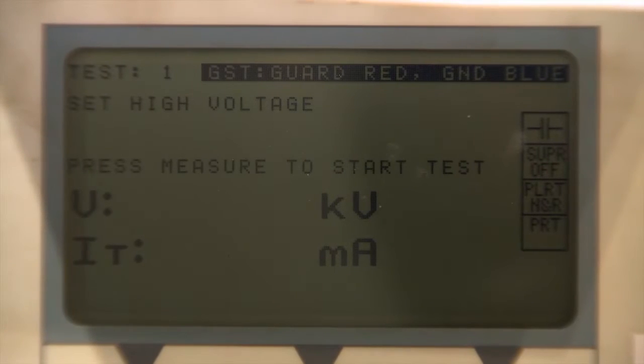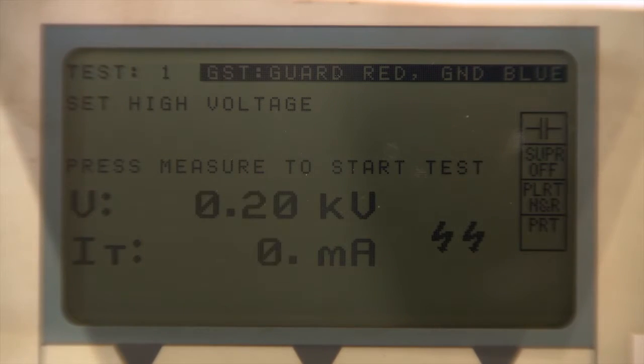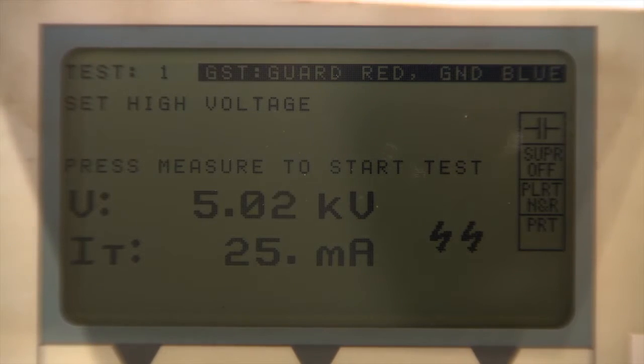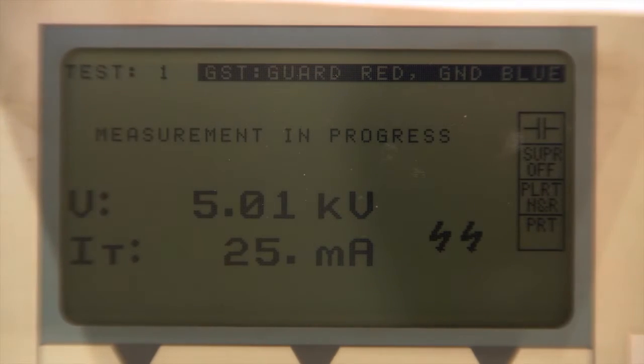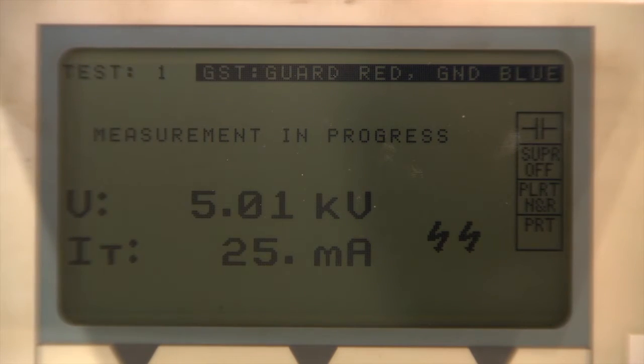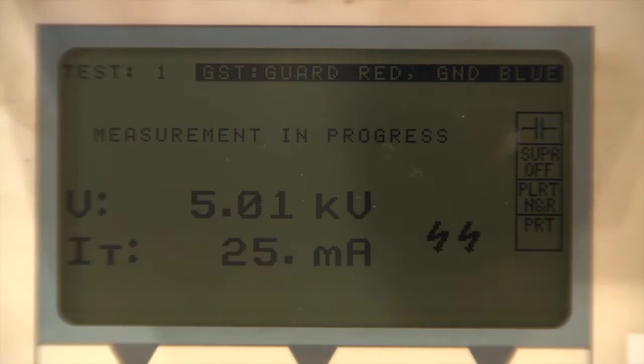Perform the C1 plus C2 GST test using the Biddle test set and using the same procedure that was used for the initial electrical testing before the bushing was refurbished. This test is executed using a voltage of 5,000 volts.